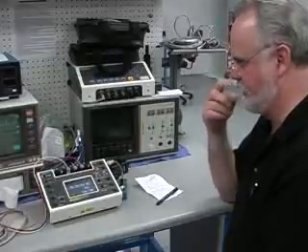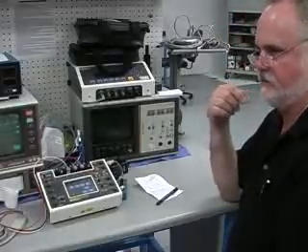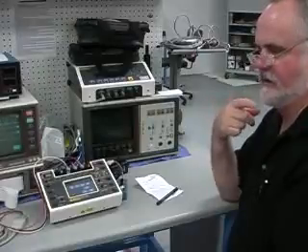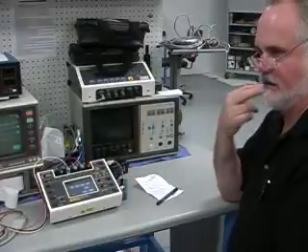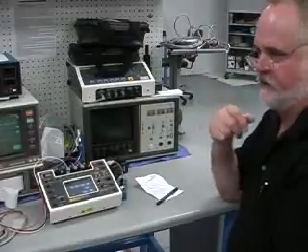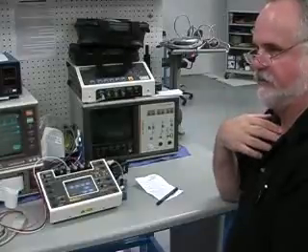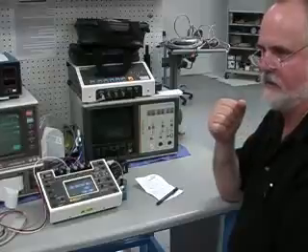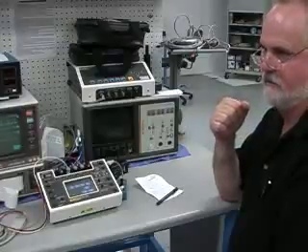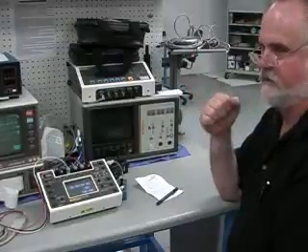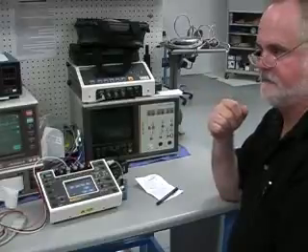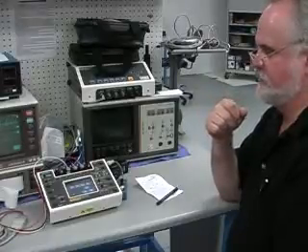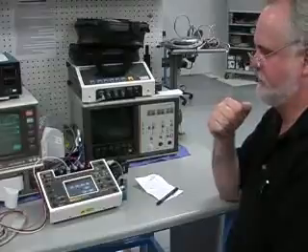Right now we don't do anything for end-tidal CO2, which is the concentration of CO2 in your exhaled breath. But all the companies that sell that equipment basically just use a static calibration for gas samples, and that seems to be adequate for that purpose. So most of the things we've got pretty well covered.